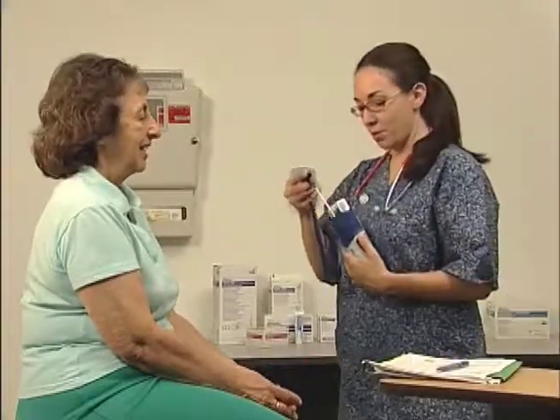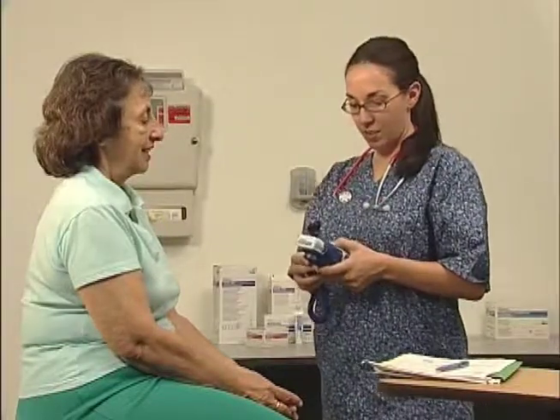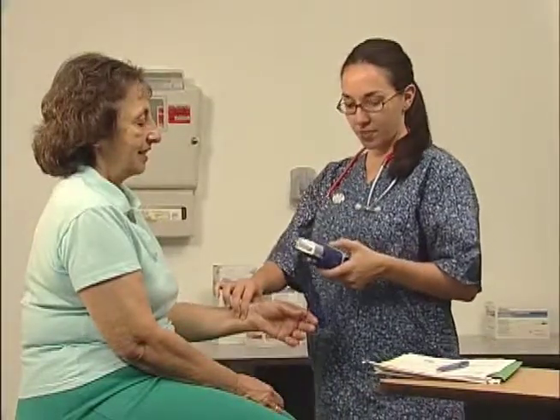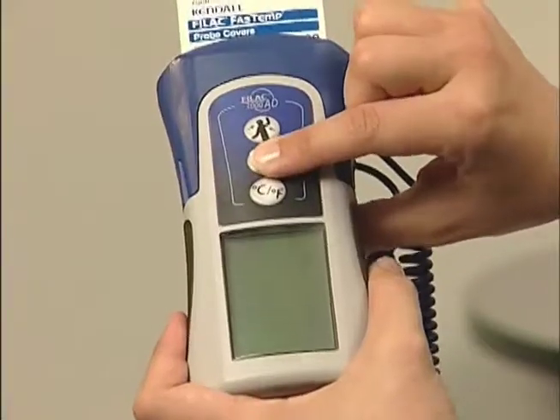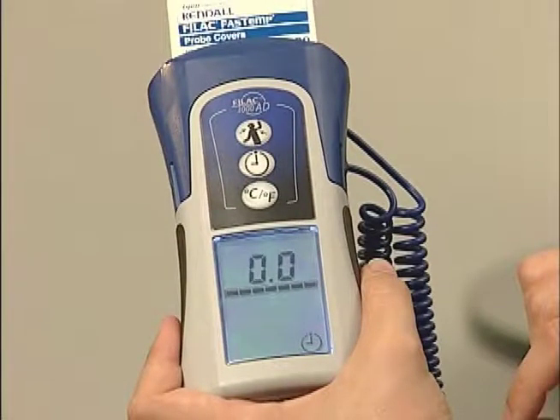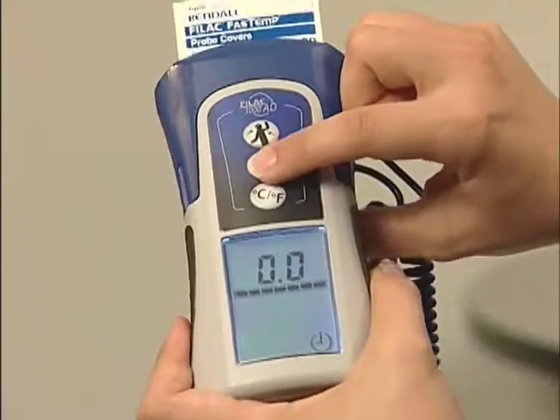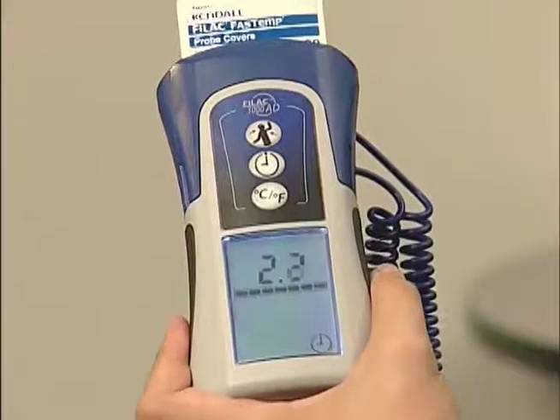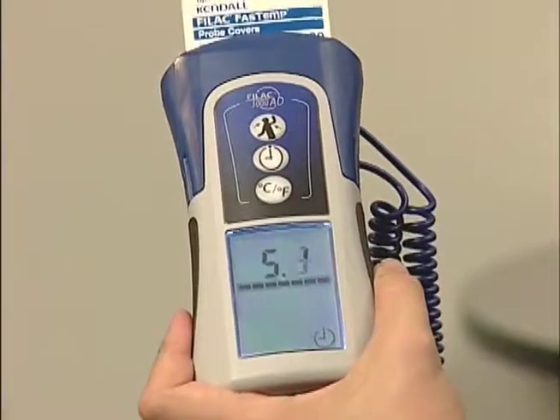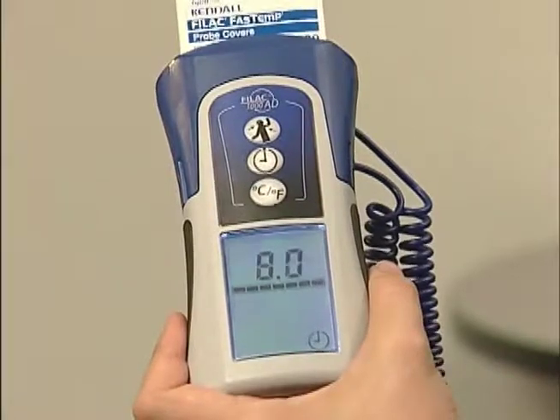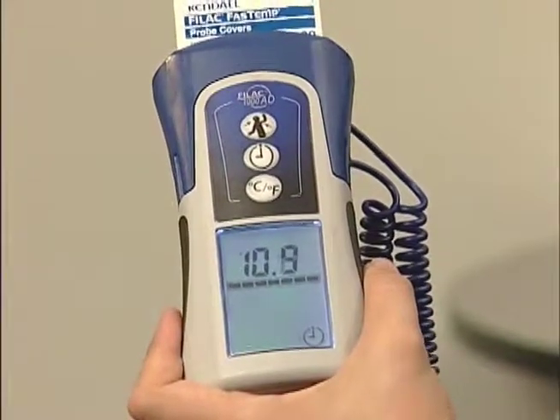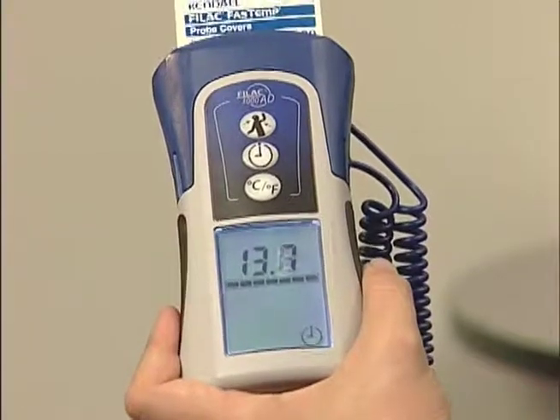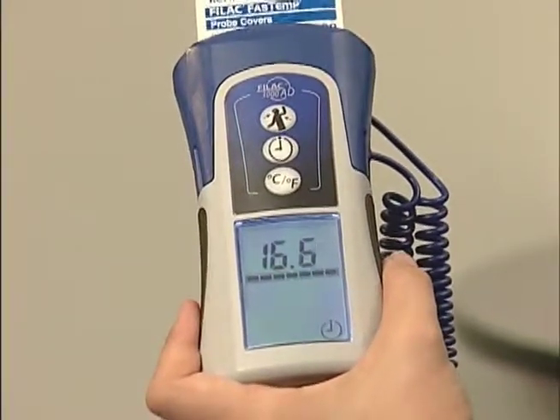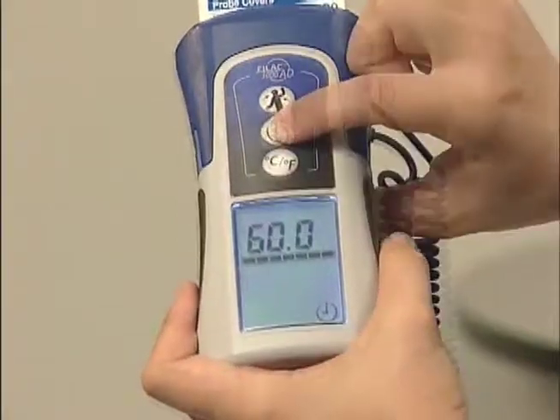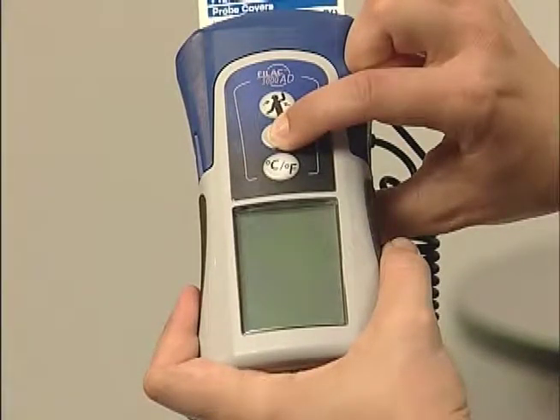The Filac Advanced Thermometer includes a convenient pulse timer to help clinicians measure a patient's pulse rate. To activate the timer, leave the probe in the isolation chamber and press the pulse timer button once. A clock icon and 0.0 will appear on the screen. Press and release the pulse timer button a second time to start the timer and elapsed time display. A beep will sound at 15 seconds, two beeps at 30 seconds, one beep at 45 seconds, and two beeps at 60 seconds. This timer will help clinicians determine the patient's pulse rate per minute. The timer will automatically stop at 60 seconds. Press the pulse timer button a third time to shut off the unit.